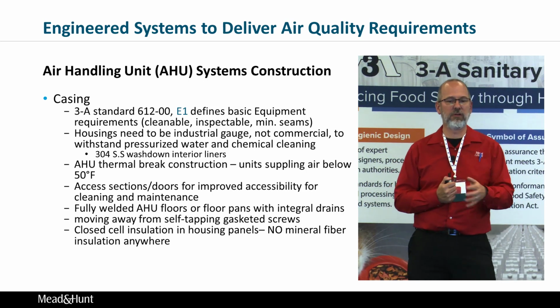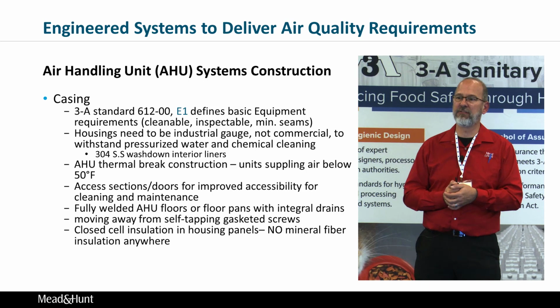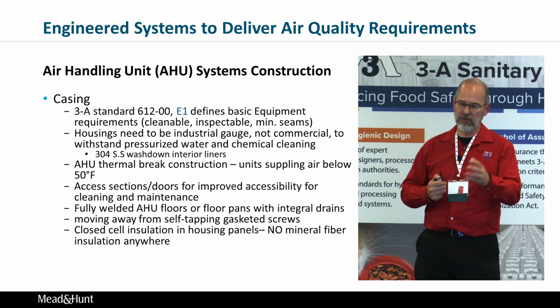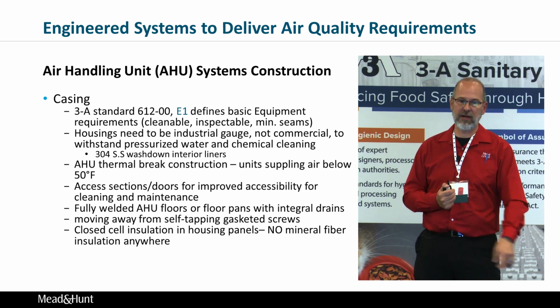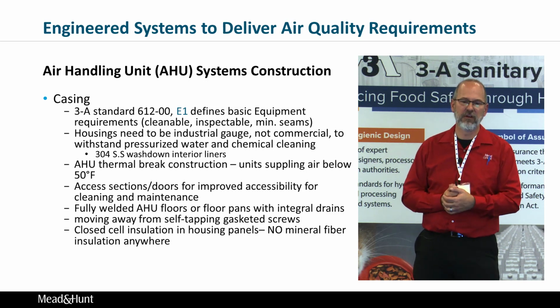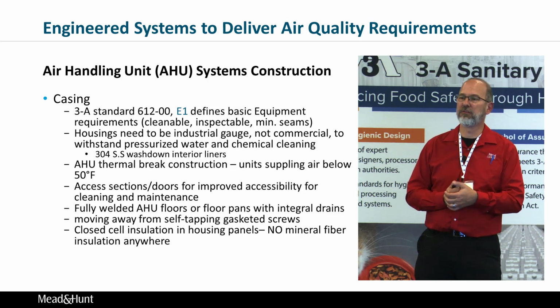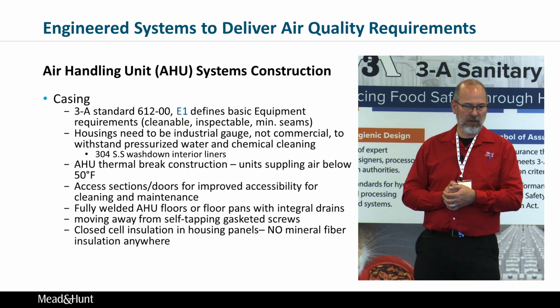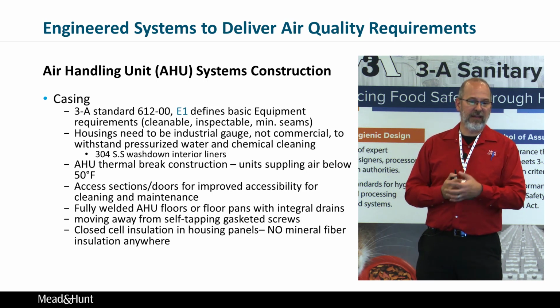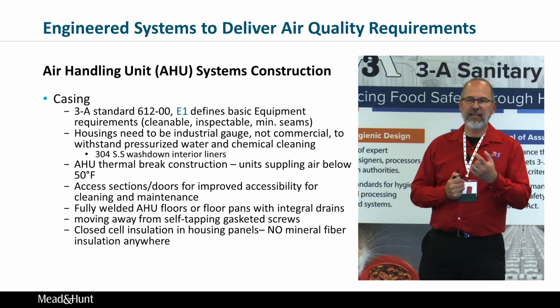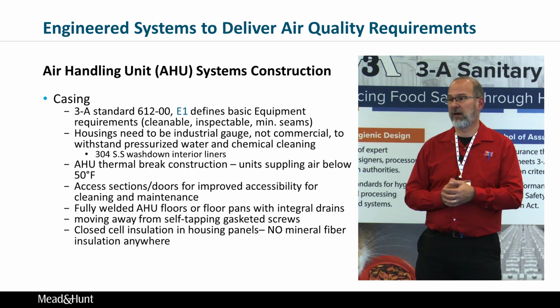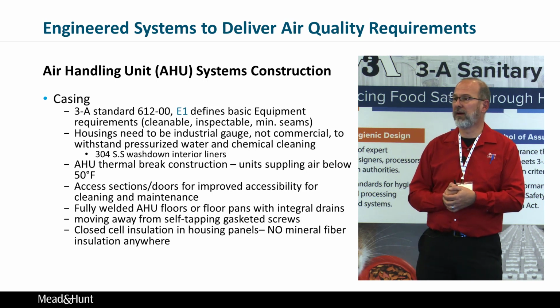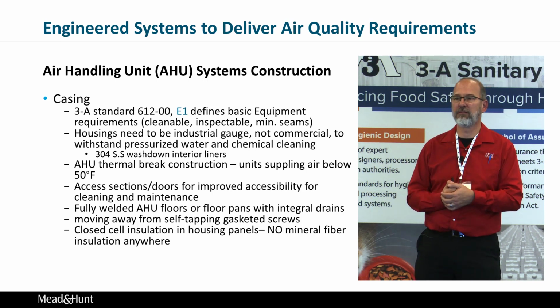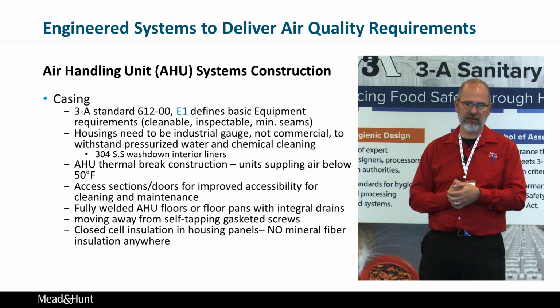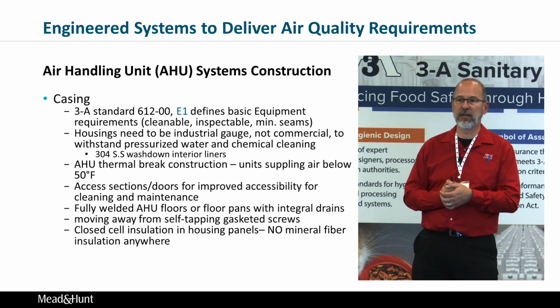We also like to see fully welded floors and drain pans in each section of the unit, so when you go to clean it out, the water will drain into the pitched floor and then run out drains. And you can see in the image there, the bottom of the unit running horizontal is a common drain pipe. Okay. And finally, the insulation in the cabinet should be closed cell, polyiso, polyurethane, or polystyrene, not a mineral fiber, because that is porous, and if you do have a breach in the lining of the unit, you don't want water to get in there and collect and grow mold.